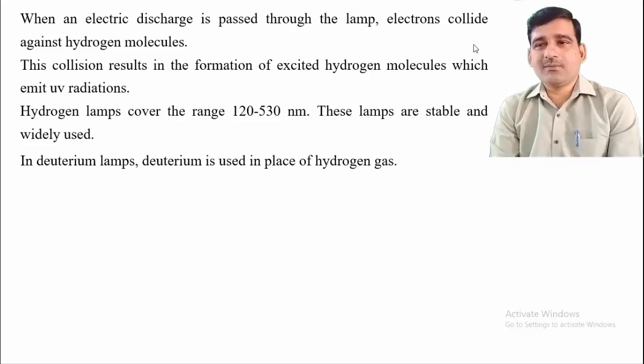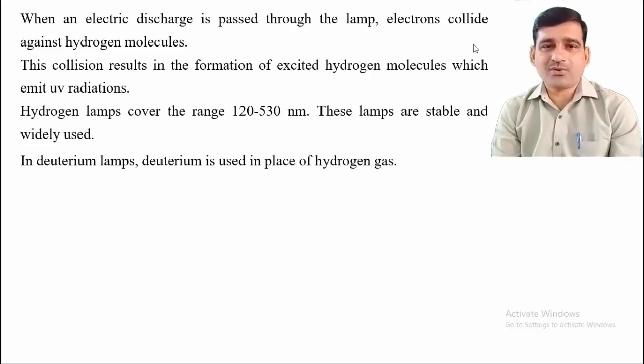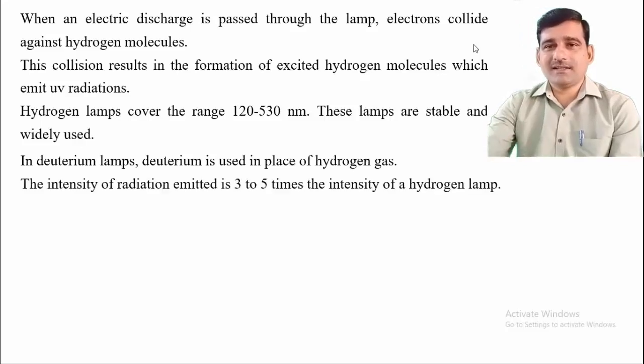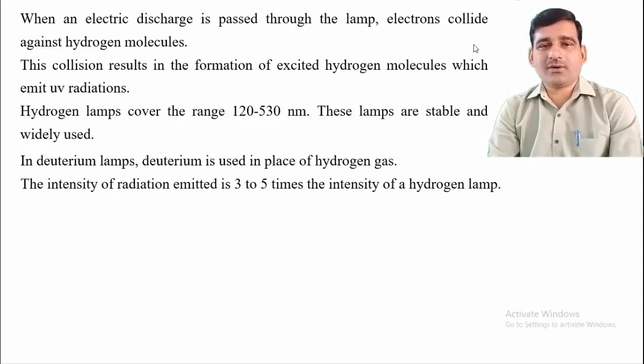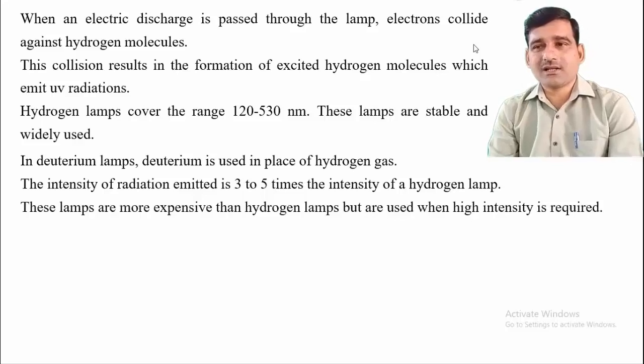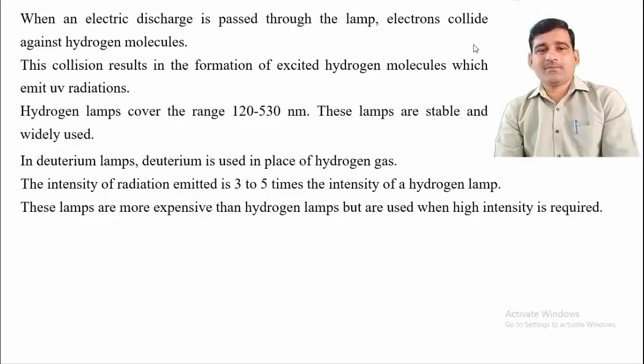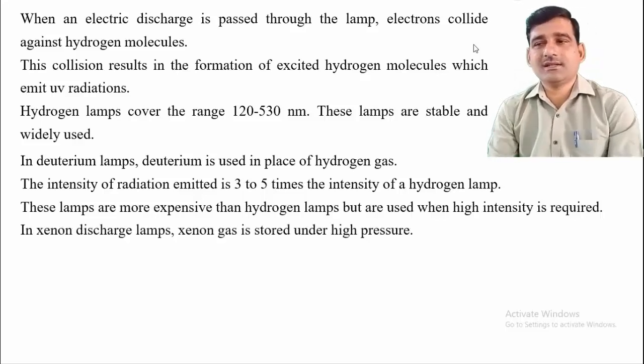In a deuterium lamp, deuterium gas is used in place of hydrogen. The same phenomenon occurs: electrons collide with deuterium molecules, causing excitation, and UV radiation is emitted on return to ground state. The intensity of the deuterium lamp is 3 to 5 times greater than that of the hydrogen lamp. Although more expensive, the deuterium lamp is mainly used in spectrophotometers when high-intensity UV radiation is required.